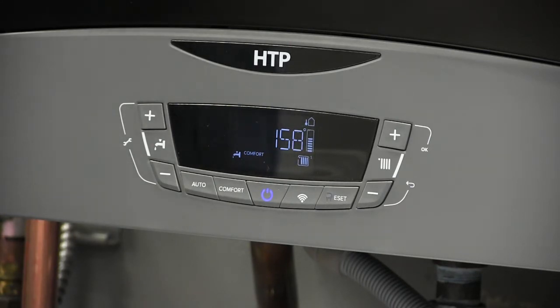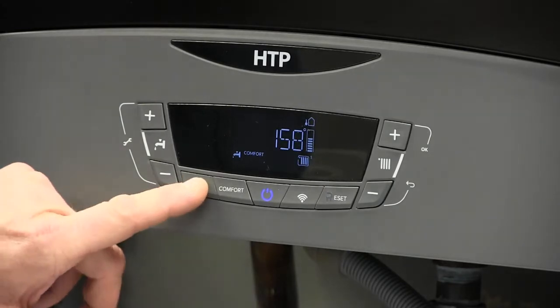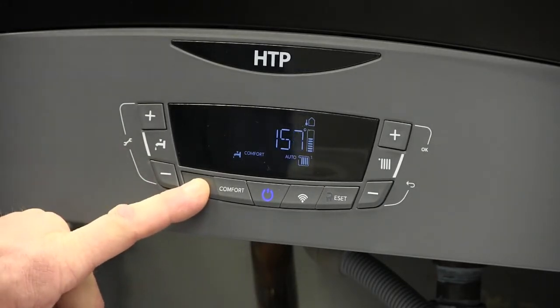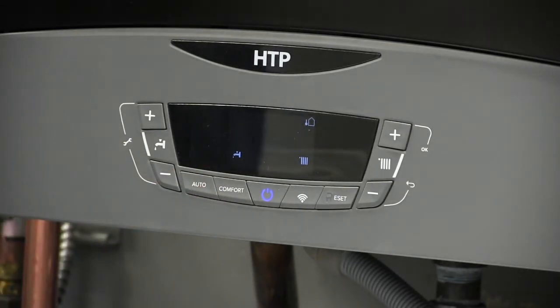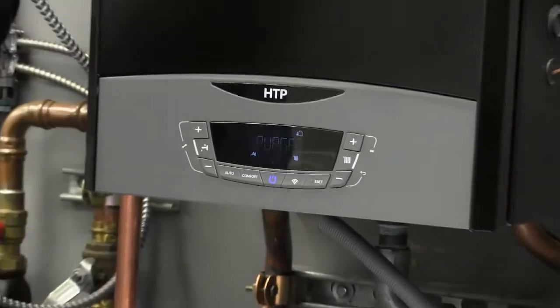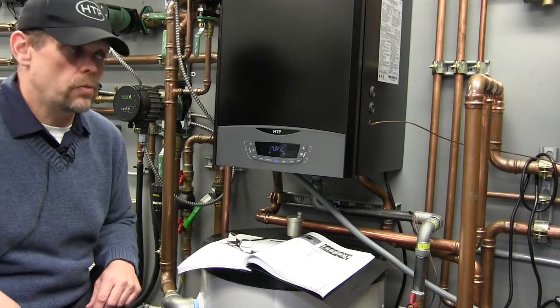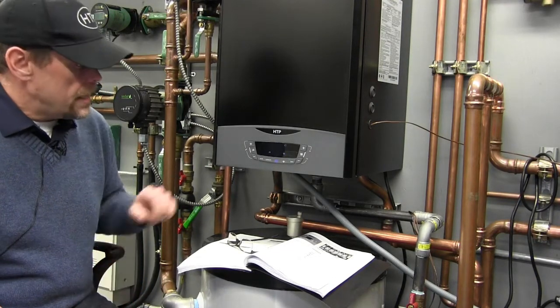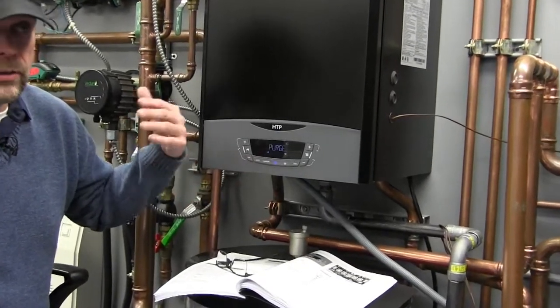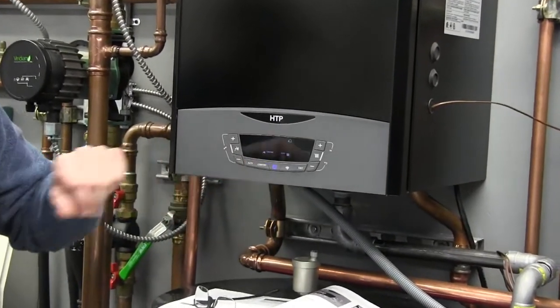The auto button, however, is multifunctional in the fact that it can initiate a purge function. So if we depress the auto button for approximately 5 seconds, we can engage a purge cycle. That will shut the burner off and keep the boiler pump running, and if it's attached to other pumps, it'll keep those pumps running to allow the system to be purged out. That's the 6-minute purge. If we do not need a full 6 minutes, of course, we can hit the auto button and go out of the purge function.